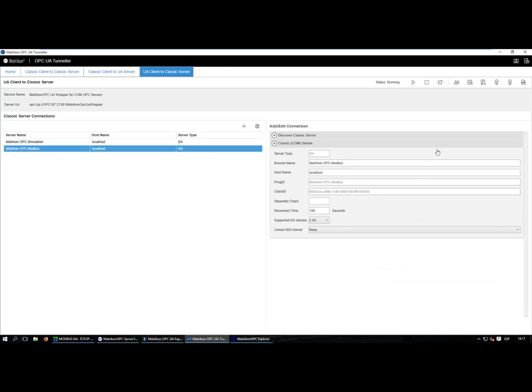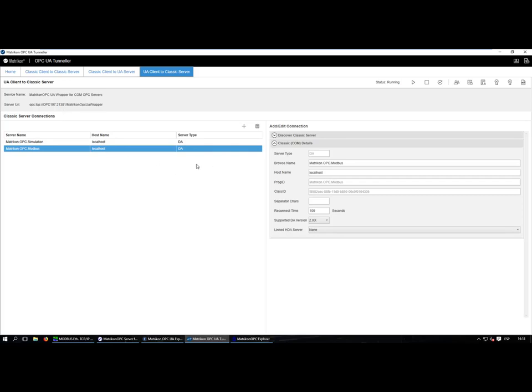I'll restart the service after adding both servers. In OPC UA technology, security is based on digital certificates. In this presentation I'll show you how to connect without security first, but for a secure connection you need to exchange certificates with the OPC UA client. Here you can manage the certificates and see the trusted and rejected certificate stores. I can see the certificates I have in the certificate store, and both OPC classic servers have been added for conversion to UA.